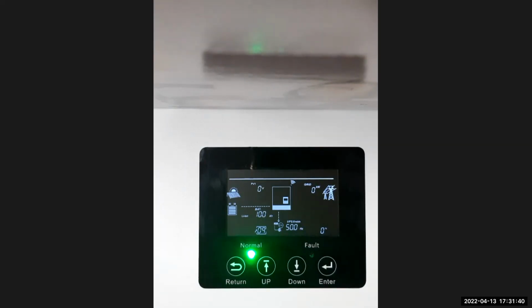Then, when you're on lithium mode, you won't be able to access 7 and 8. Number 7 and 8 is your float voltage and your charge voltage. That you can't set on a lithium battery that's communicating. That's between the battery and the inverter that is communicating. So if you set number 3 to lead acid, you'll be able to enter 7 and 8. That's my charging and my floating voltage. So that's why you can't see it at this moment here.